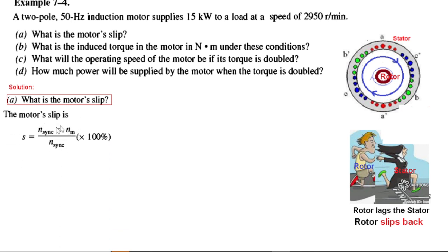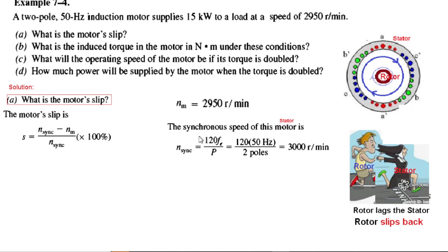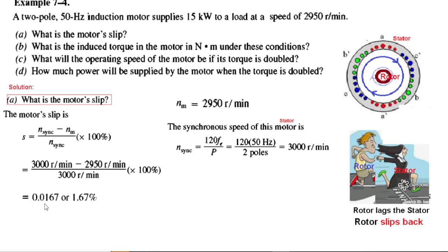The equation for slip is: slip = (n_sync − n_motor) / n_sync × 100%. The motor speed is given as 2950 RPM. We calculate sync speed using the formula: n_sync = 120 × f / P = 120 × 50 / 2 = 3000 RPM. From here, slip = (3000 − 2950) / 3000 = 0.0167, or 1.67%. That is the first part.